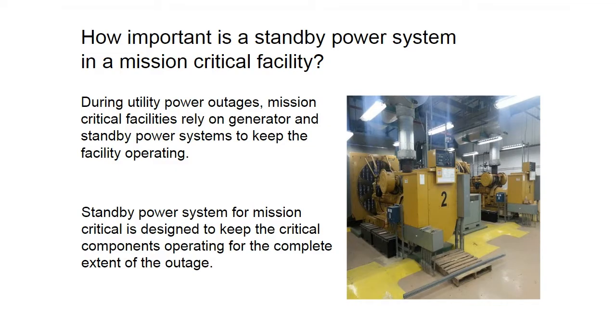So how important is a standby power system in a mission-critical facility? Basically, if you're a facility operator, the power goes out, the 911 facility, maybe you're a doctor in operation, that 10 seconds or less while you're sitting there waiting for that power to come on, that's the importance of that critical standby power system. It becomes the most important system in that facility. So basically, during a utility power outage, the mission critical facility relies on that generator and that standby power system to keep the facility operating.